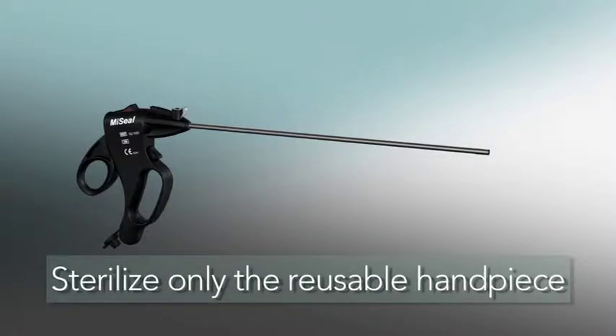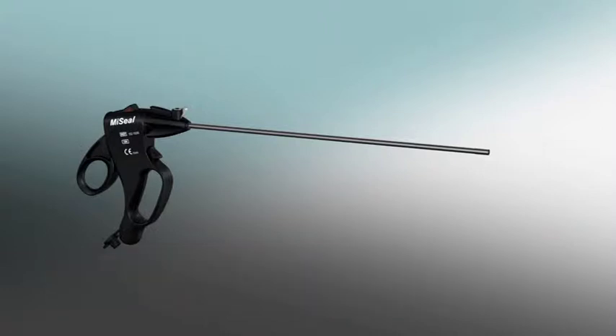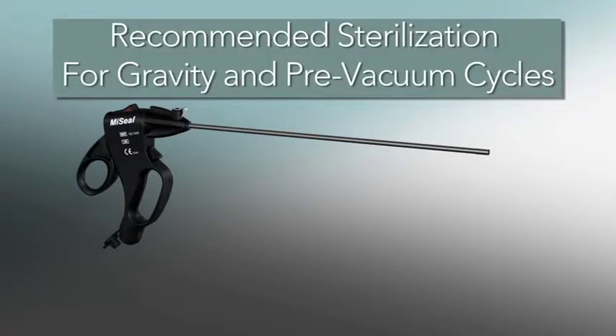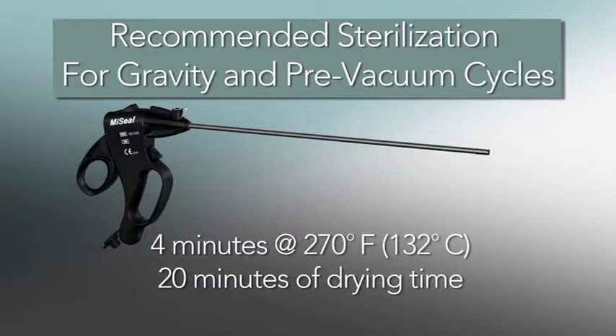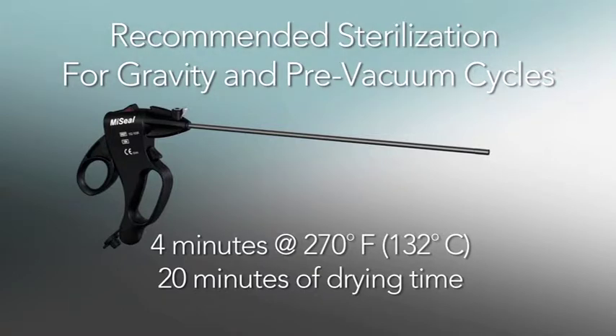Remember, only the reusable handpiece may be subjected to the sterilization process. Starion Instruments recommends using the following validated steam sterilization cycles as minimum guidelines: 4 minutes at 270 degrees Fahrenheit or 132 degrees Celsius, and 20 minutes of drying time.